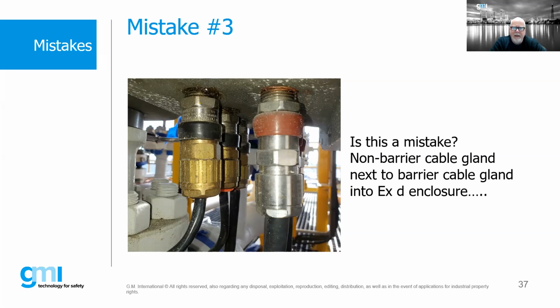So think of it this way: the cables on the left-hand side, if those leads are going off 20 or 30 feet, that gland is perfectly acceptable. The gland on the right, if it's going into a device located 5 feet away, would be the appropriate gland. If you're not aware of these things and you just come look and say, wait a minute, different glands going into the same enclosure - that's why it's important to understand the requirements in the -14 standard and stay up to date with the latest rules and regulations.